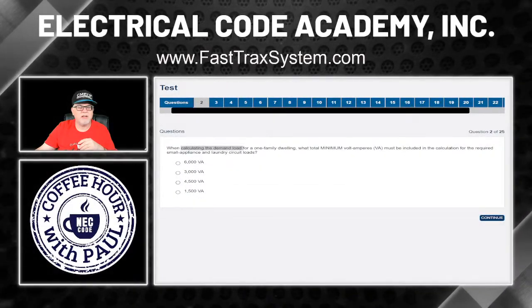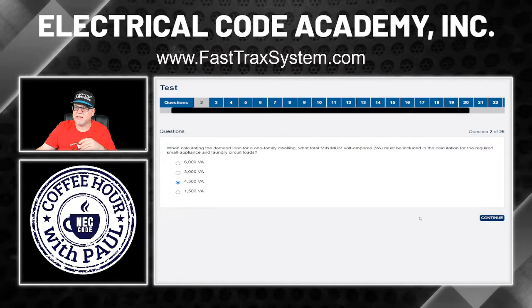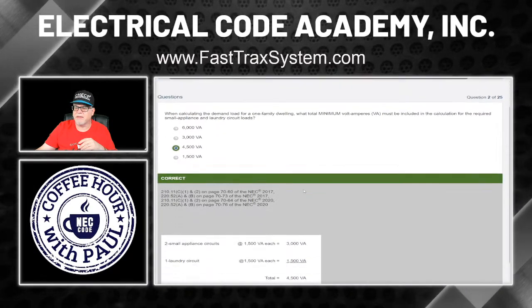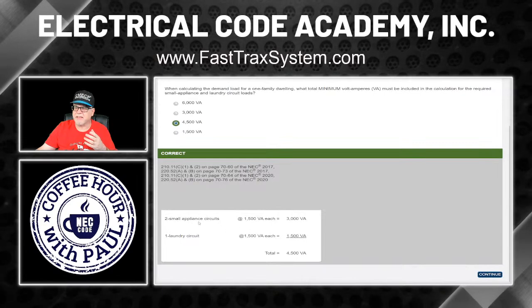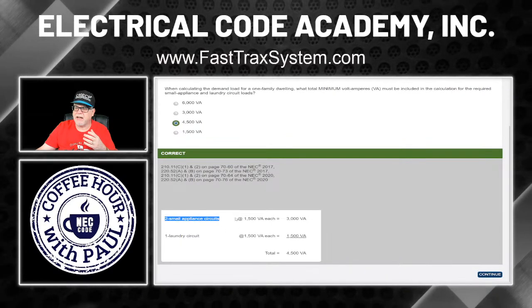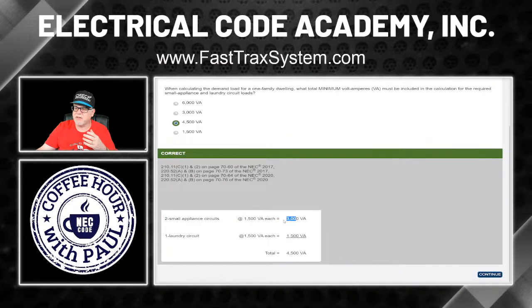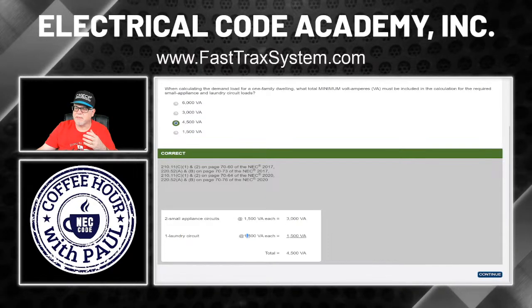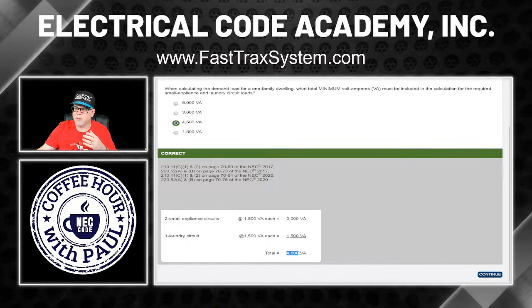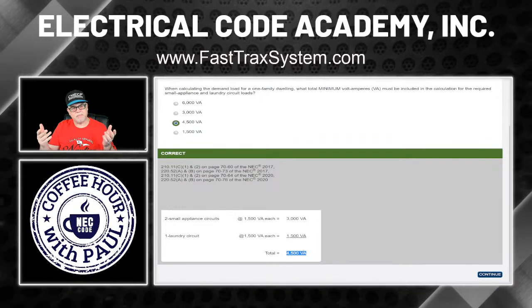Here we're at the question. And let's go on and click that. And there you go. That's correct. And there's the math logic right there. 2 small appliances, 1,500 each. That's 3,000. And then you have the 1 laundry, 1,500. Okay, so 4,500 total, and that was our answer.